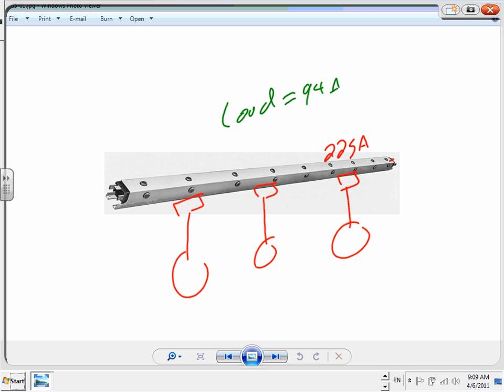So here's a question that you're going to ask yourself. I plug it in. I need a cable tied to it, and I need to take it all the way to the overcurrent protection device in the panel, right? This has to be fed from somewhere. So I need a cord to feed it, and I need an overcurrent protection device. In a case like this, guys, if your load is 94 and the smallest that you can buy is 225 amp, it makes a lot of sense to make the cable 100 amp and the overcurrent protection device 100 amp. Is that okay? A 100 amp overcurrent protection device feeding a 100 amp cable to feed a 225 amp plug-in or trolley busway. That's okay.